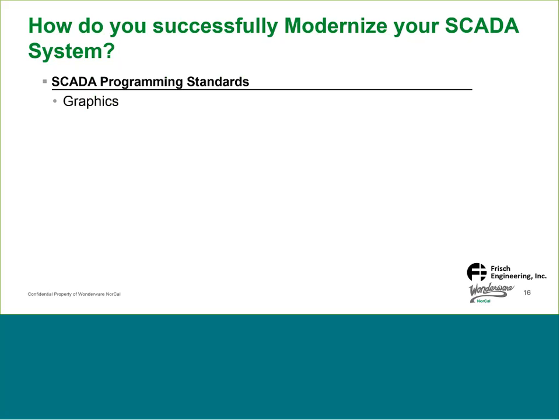And this could include your graphics, and you would make note of the system, maybe your facility's overview, your process unit levels that you're going to have in the system or that you do have, and identify the equipment, manual or automatic control, and then possibly your control set points, your screen layout—your header and footer areas, what size they're going to be, what they're going to look like, your main process area, your graphic symbols, going from your process lines, equipment, your text.